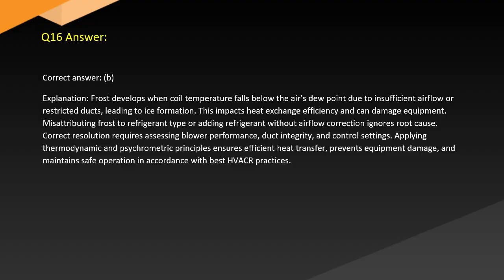Answer. Correct answer: B. Explanation. Frost develops when coil temperature falls below the air's dew point due to insufficient airflow or restricted ducts, leading to ice formation. This impacts heat exchange efficiency and can damage equipment. Misattributing frost to refrigerant type or adding refrigerant without airflow correction ignores the root cause. Correct resolution requires assessing blower performance, duct integrity, and control settings. Understanding thermodynamic and psychrometric principles ensures efficient heat transfer, prevents equipment damage, and maintains safe operation in accordance with best HVACR practices.